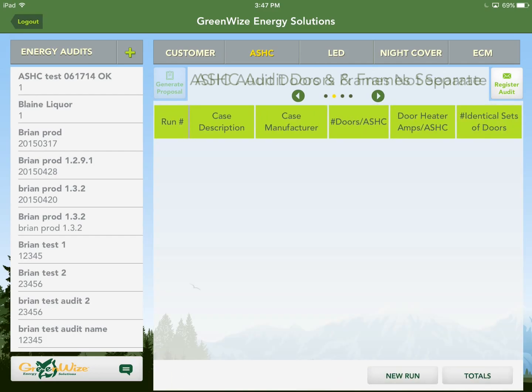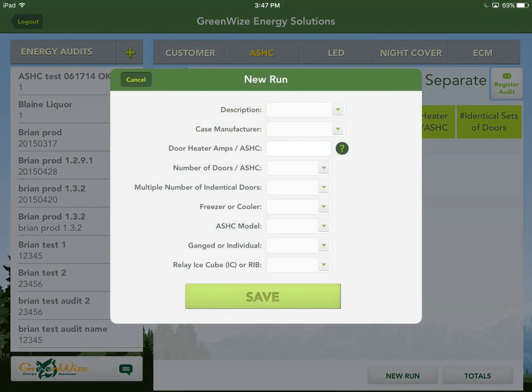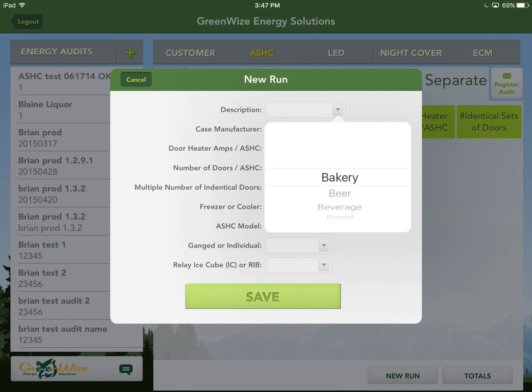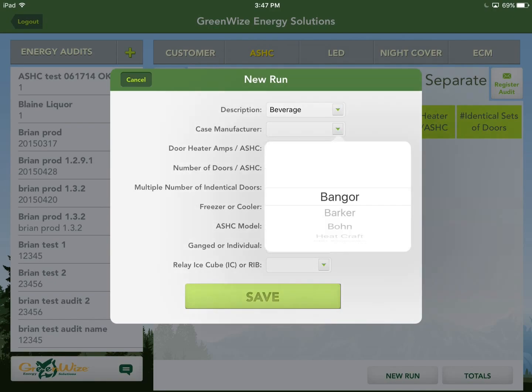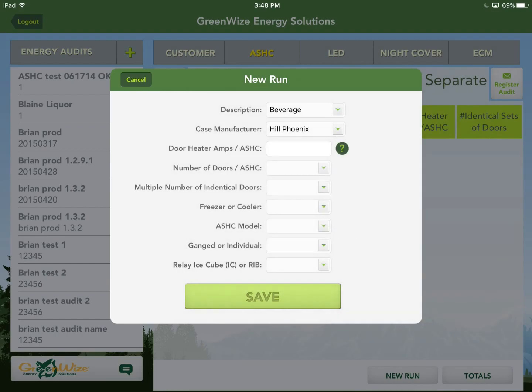On the next tab, let's say there's a walk-in beverage cooler with 16 doors — two sections of eight doors each. Call it beverage cooler. The case manufacturer isn't absolutely necessary. For door heater amps per anti-sweat heater control — this is important because if you go above 12 amps, you must use an additional controller, a RIB relay, or another type of relay to handle those amps.